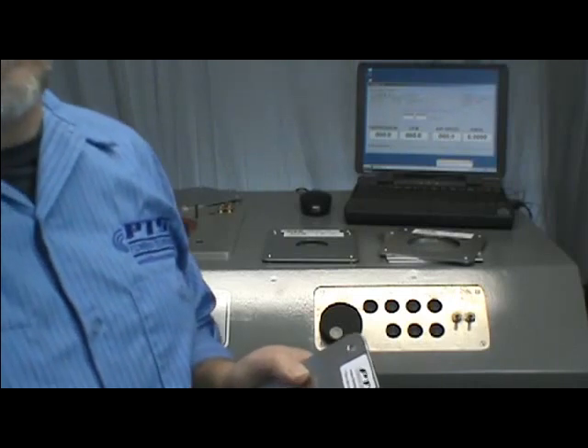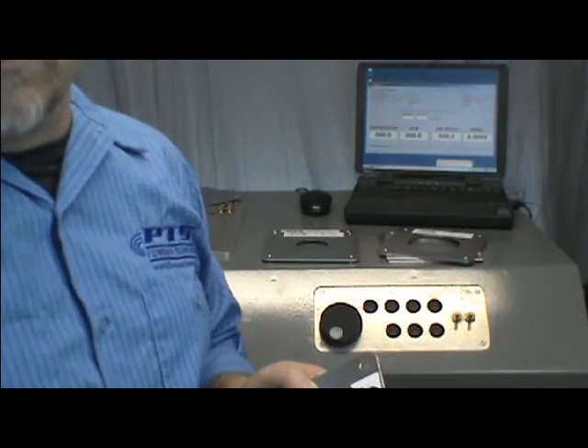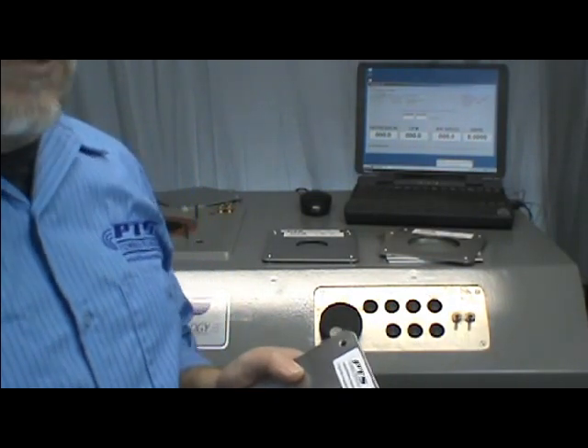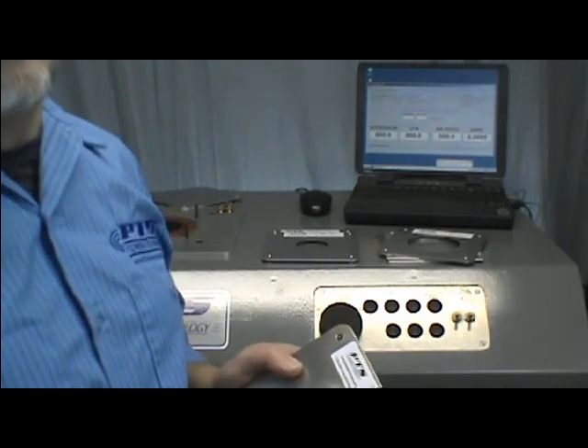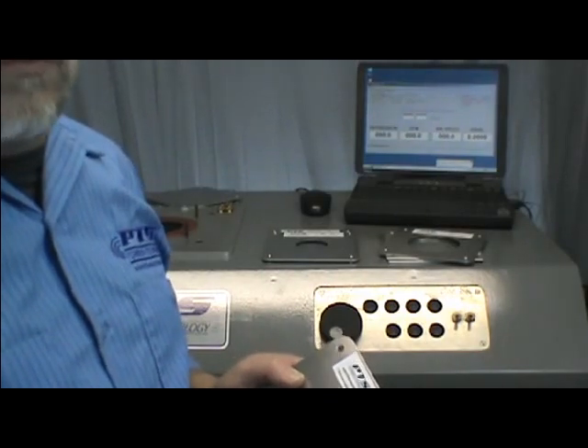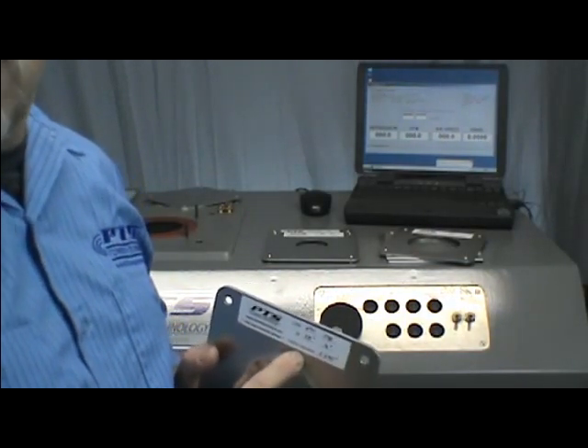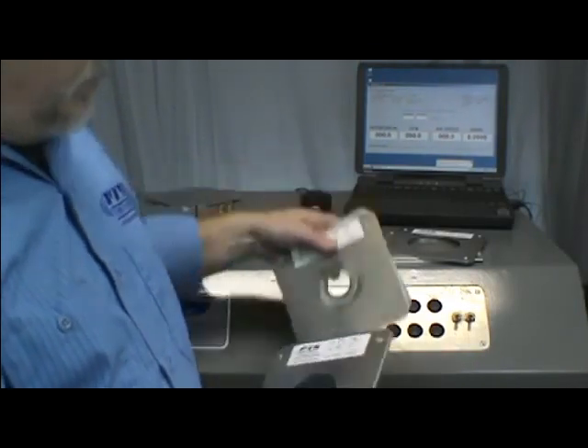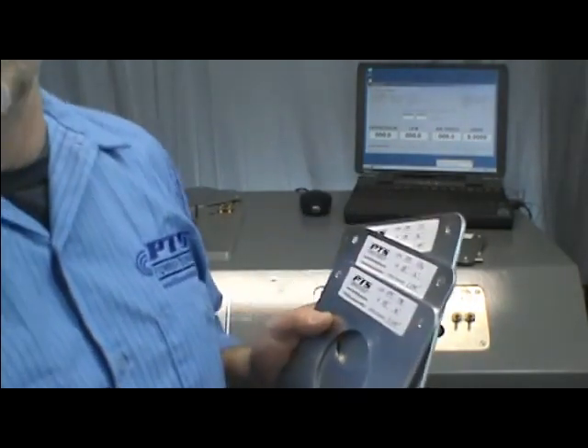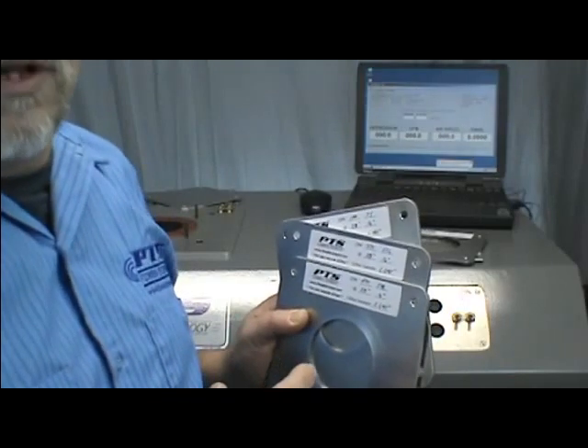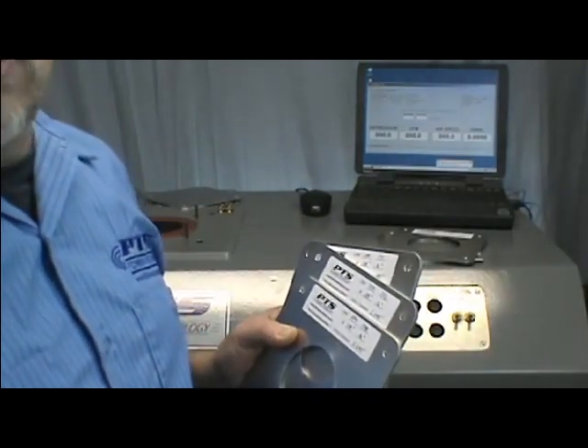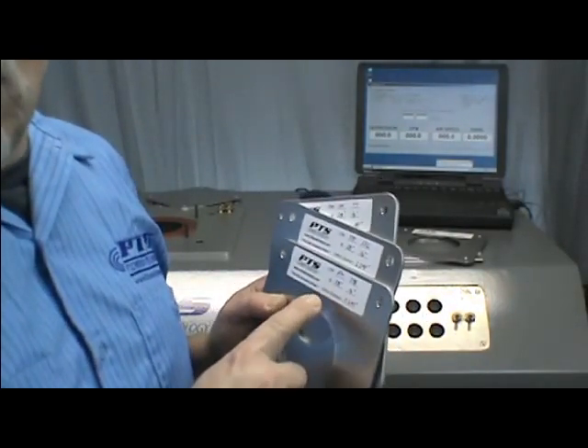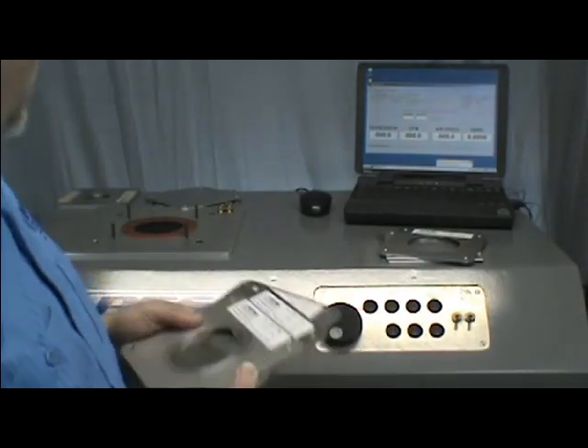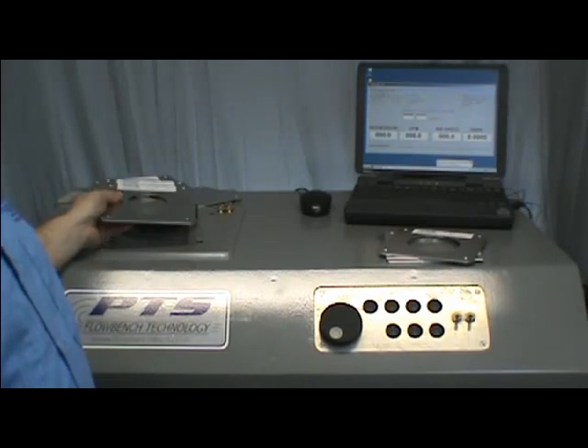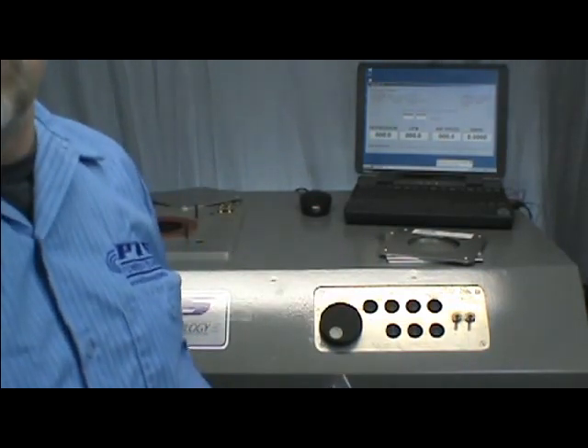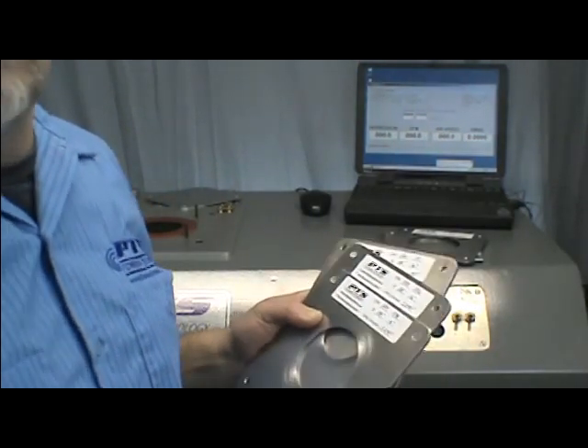It's kind of hard for people to grasp the concept as to what the difference is in that number. I have a lot of people ask me, well, I flowed that plate at 16 inches on top of the bench, and I'm like, no, no, no. That 16-inch number is your internal number. And I do it this way so that people don't have to buy multiple sets of orifice plates. So instead of having to buy 28-inch plates for on top of your bench for calibration plates and then another set of plates internally, I've worked out sets of plates that allow the same plate to work inside the cabinet or on top of the flow bench as a calibration plate. So instead of buying 8 plates, you're only having to buy 3 plates or 4 plates or whatever we determine you need for your flow bench build.